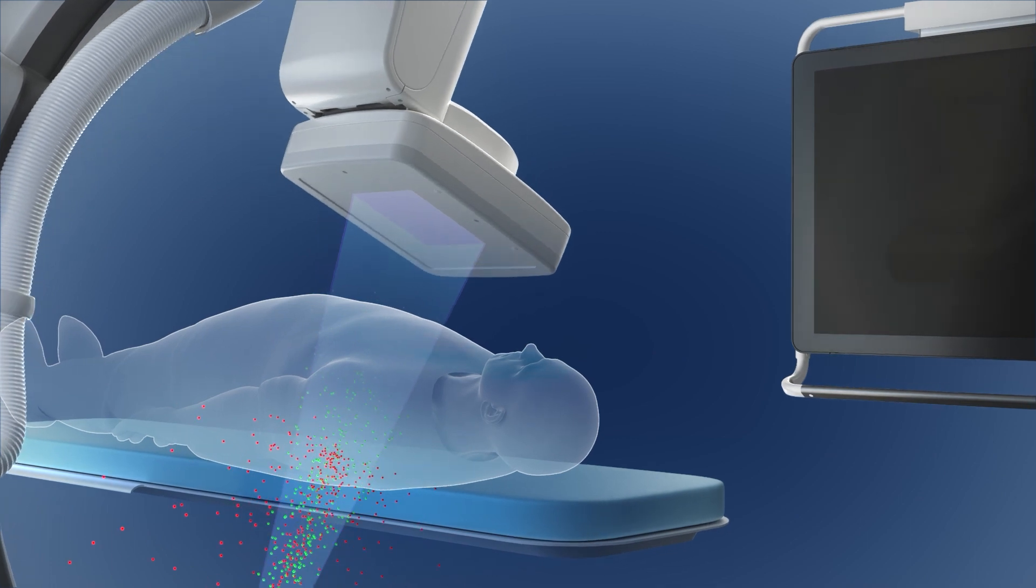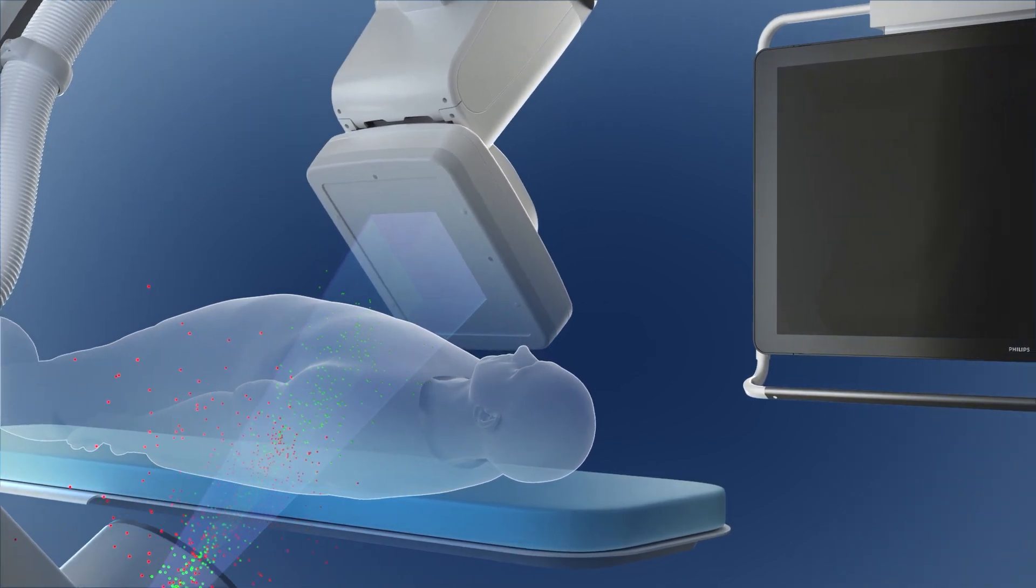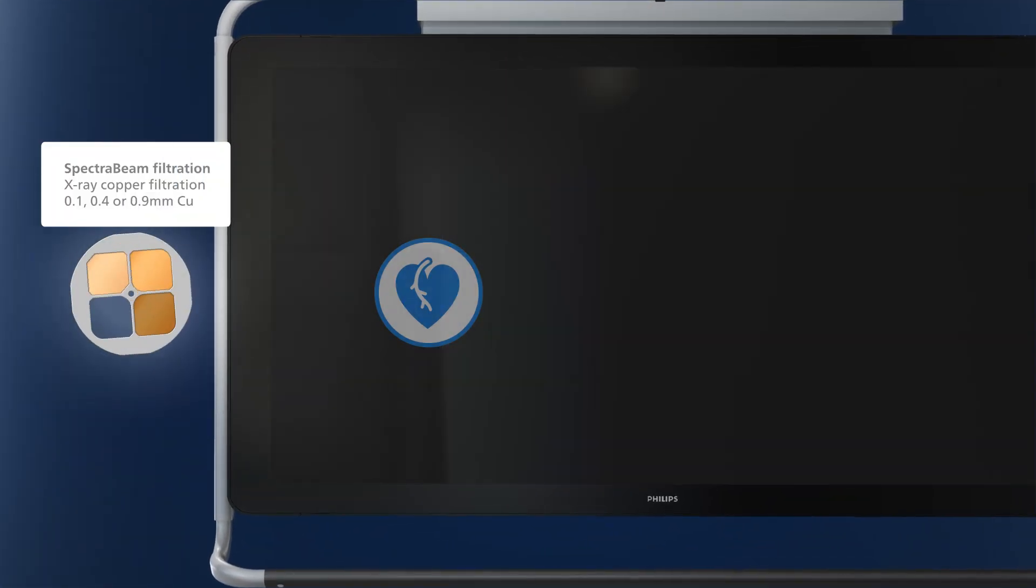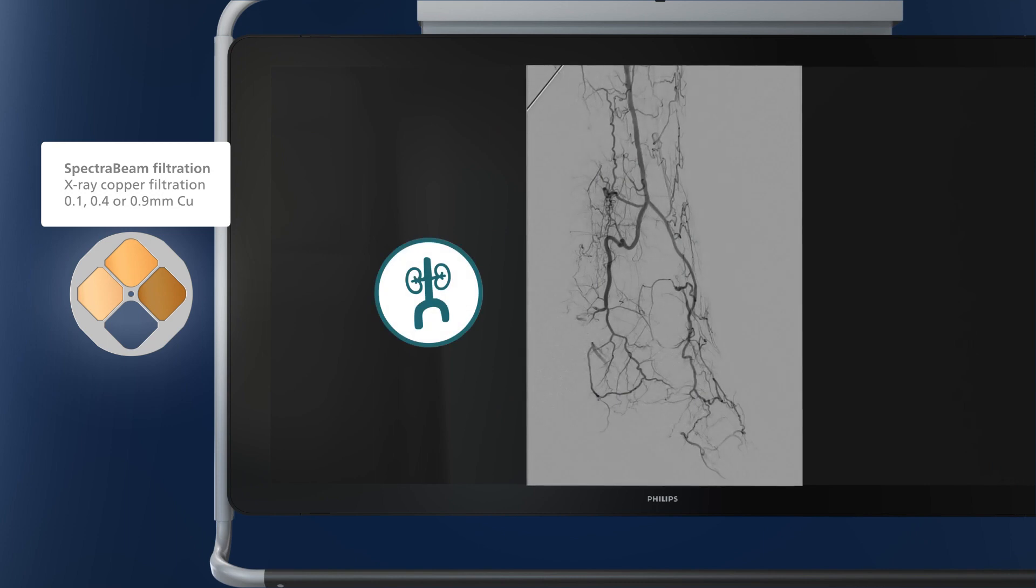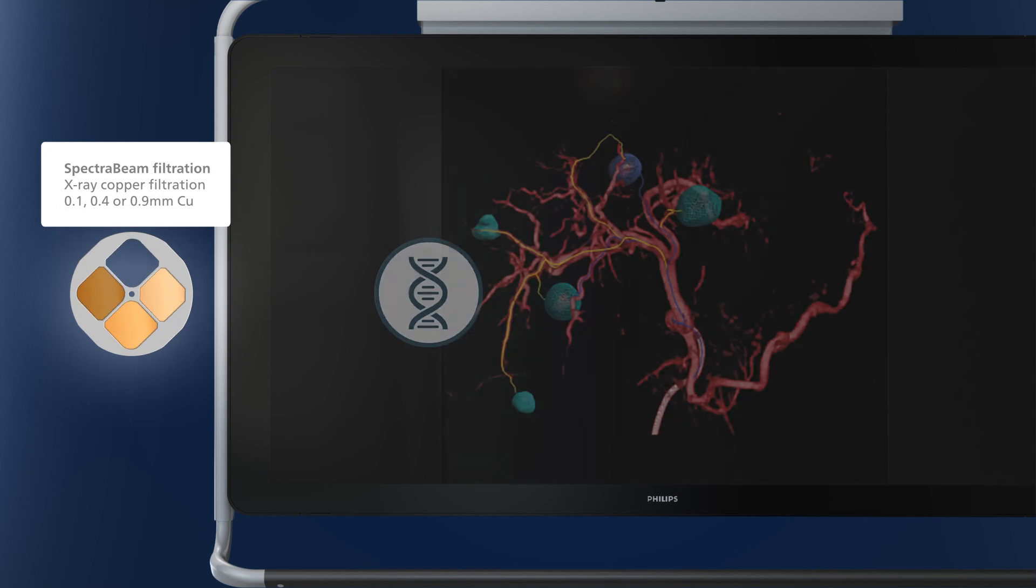Spectra beam filtration is automatically selected and applied at a constant level, resulting in a safe and predictable system behavior for all patients, including high BMI and the steepest projections, leading to excellent image quality and dose ratio tailored to the clinical application of your choice.